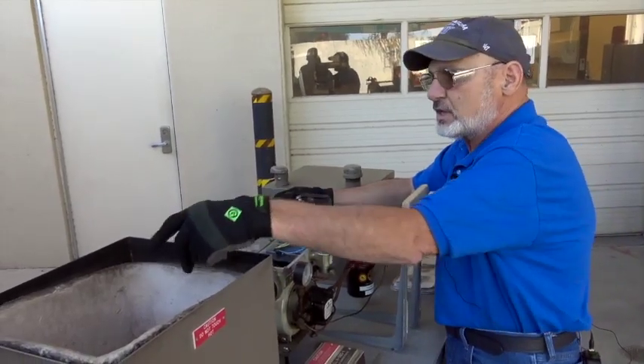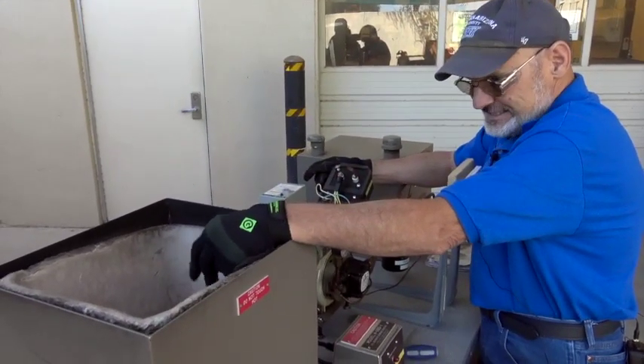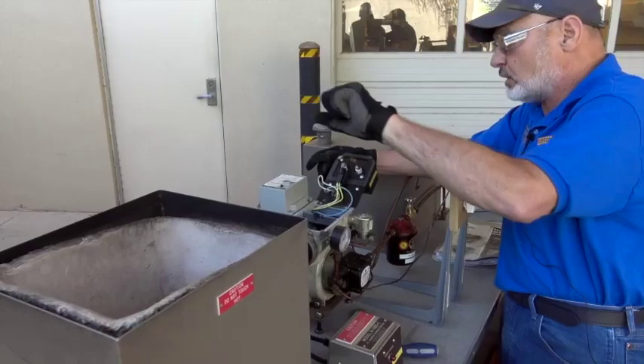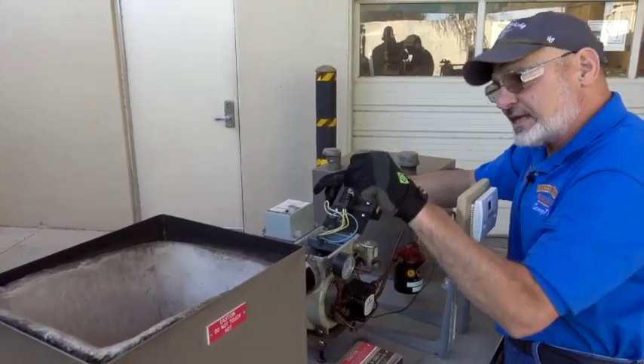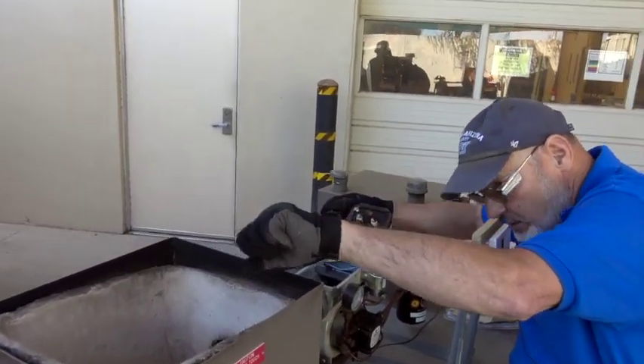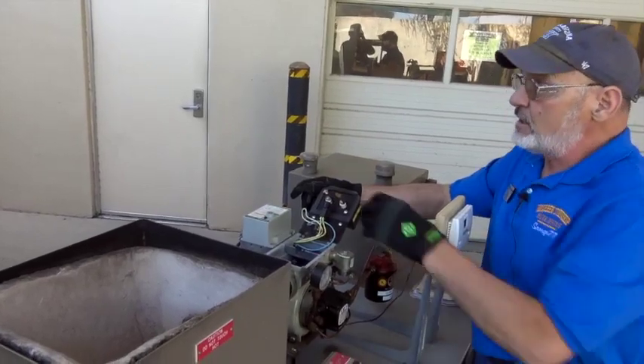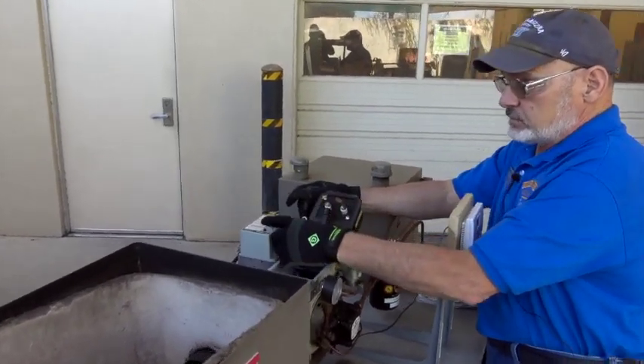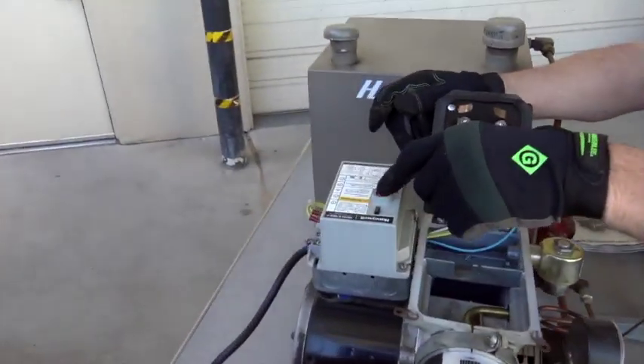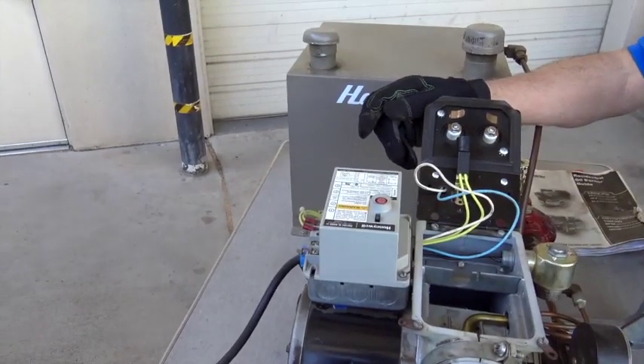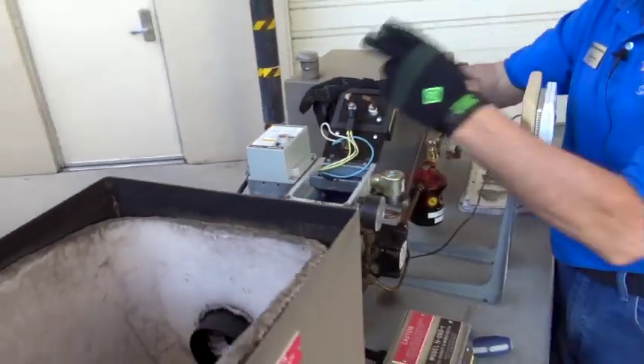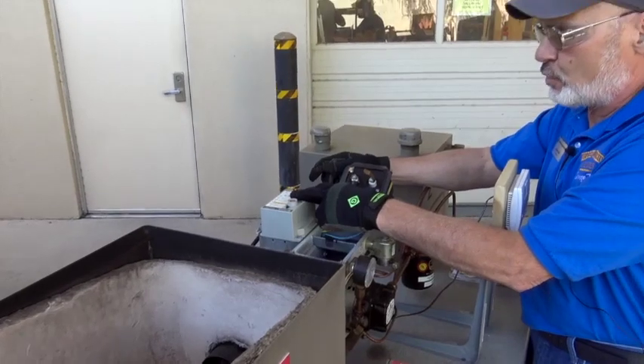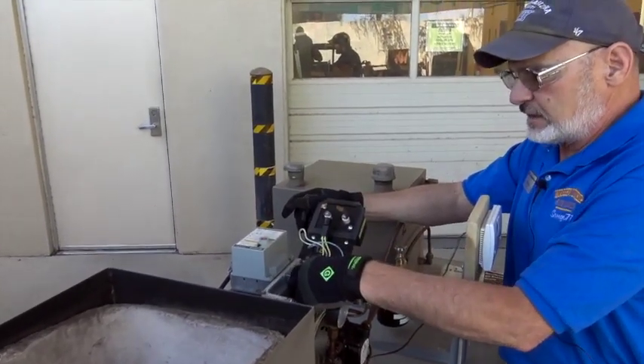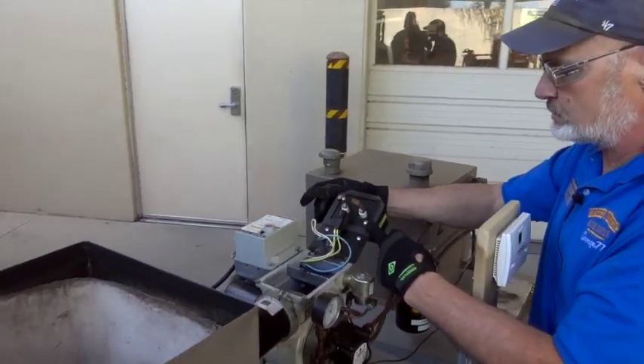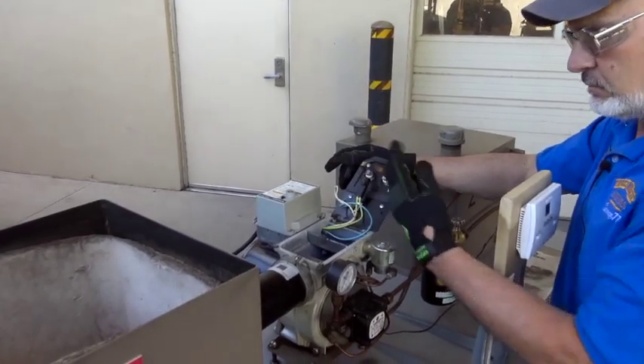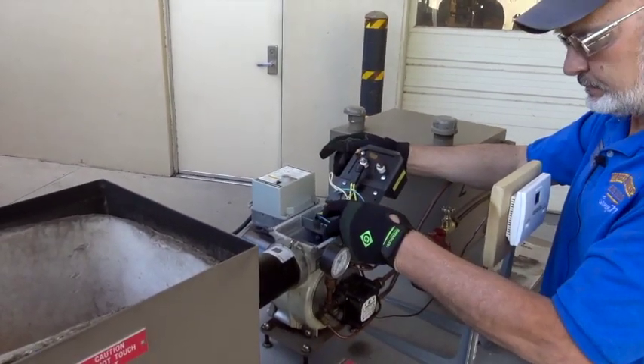So make sure you take a look inside that heat exchanger. Usually you're going to have a little cover. You can look in there, take an inspection mirror and look around in there. If you see a lot of fuel in there, that customer has reset that thing quite a few times, not just once or twice. So we understand how the primary control works. We understand how the electrode transformer, CAD cell, pump, and combustion air work.